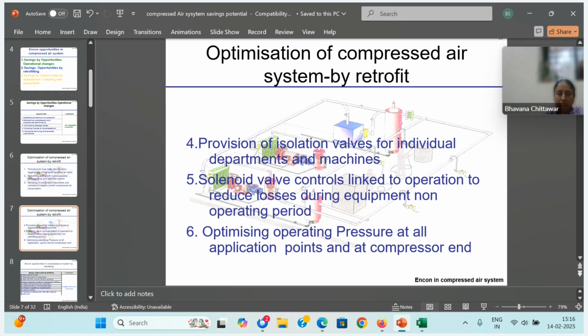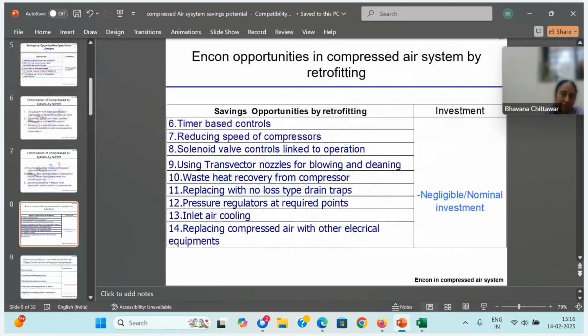And optimizing operating pressure at all points, and lastly at the compressor end. So install air pressure regulators if they are not there. You control the pressure, required pressure. Some may require only 4.5, some may require 6 kg, some may require 5.5. You control whatever is required as specified or as the equipment runs without any problem. Then timer-based control. Again, the timer. See, during lunch hours or dinner, you can have automatic control. Automatic that will stop. You don't need to intervene at all.